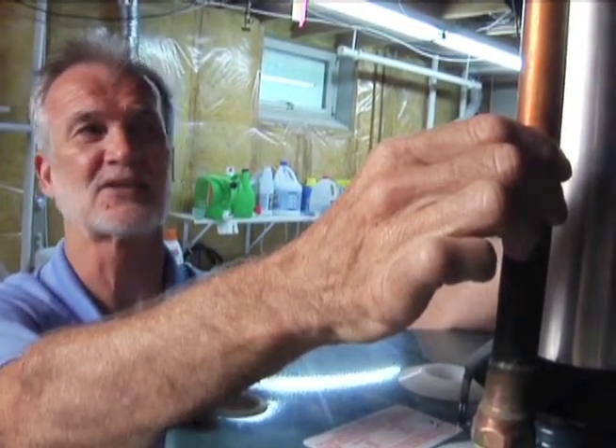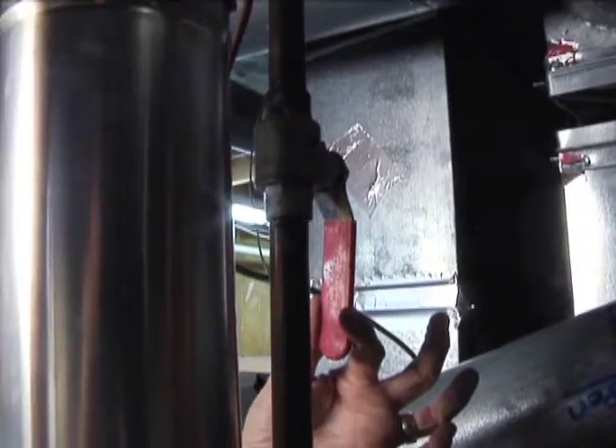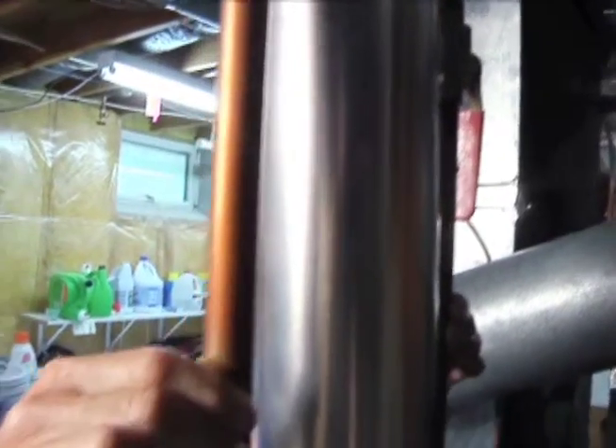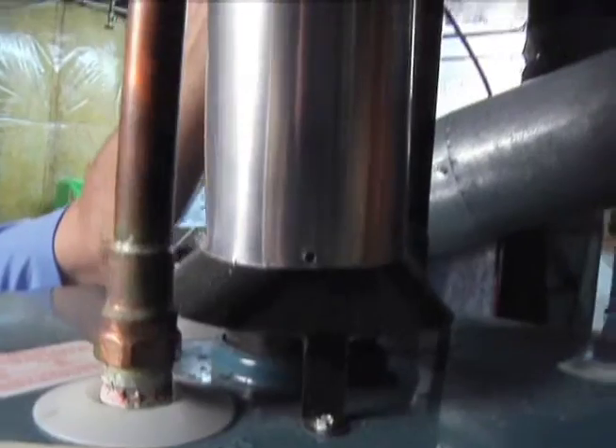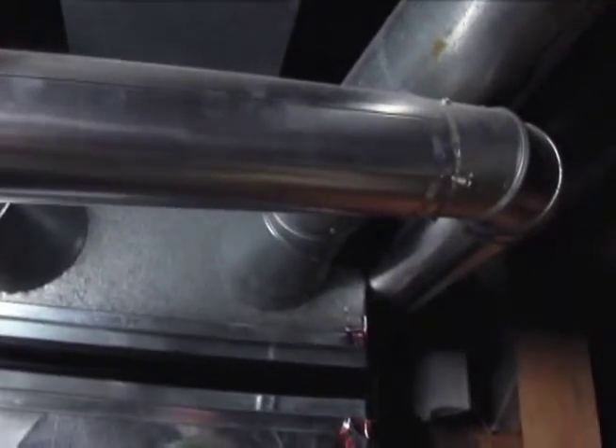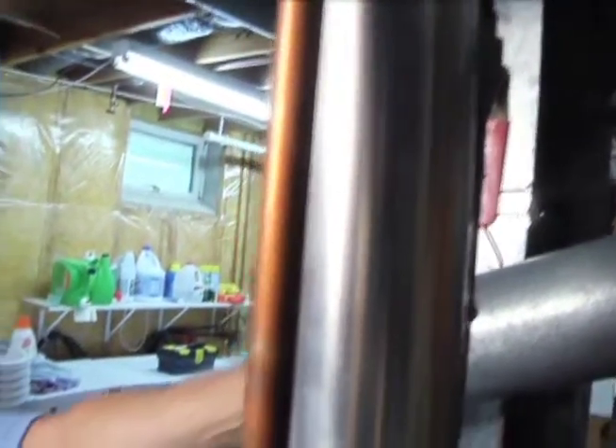As you look at water piping, many times you're going to run into valves. Here's an example of a cold water valve for the water heater. When you supply cold water into the water heater, building codes require that you have a cold water shutoff — the purpose is to isolate the fixture if you ever need to replace it. This happens to be a gas water heater. This flue pipe is a very important part of the water heater: it has to slope right, it has to be the right size, it has to have the right connections. Each connection has to have three screws — it is that important. This is a part of the system that can harm the occupants if it's not done right, so it's one of those non-negotiables.